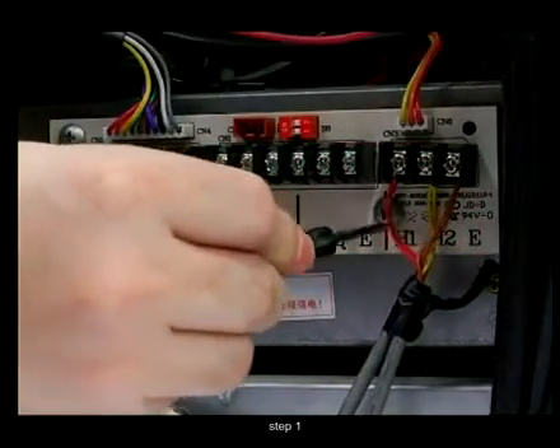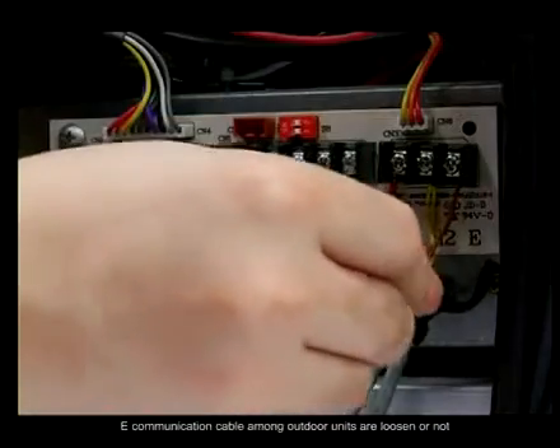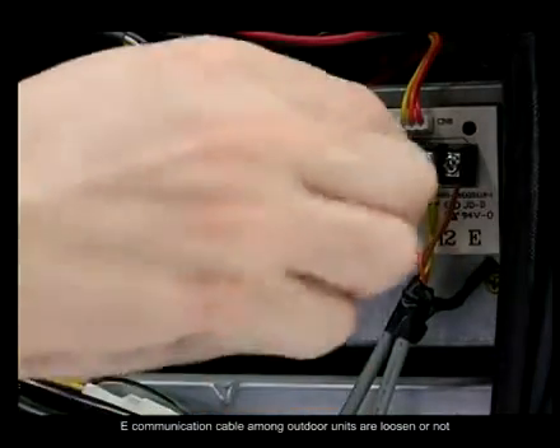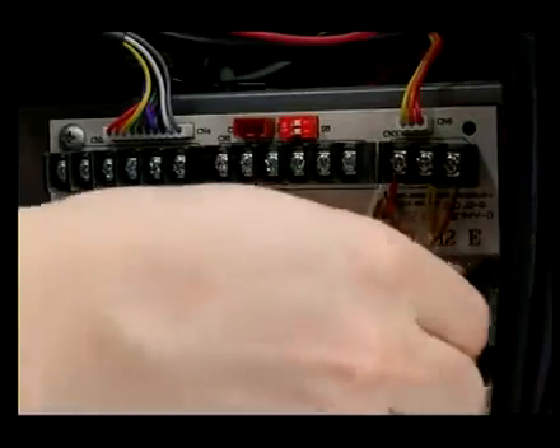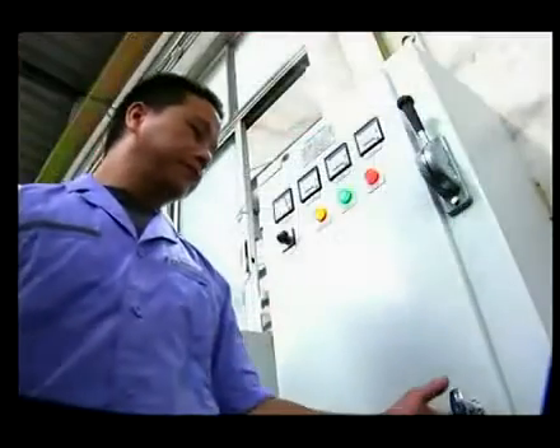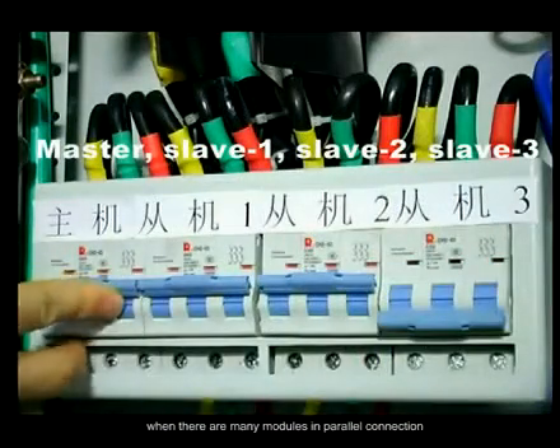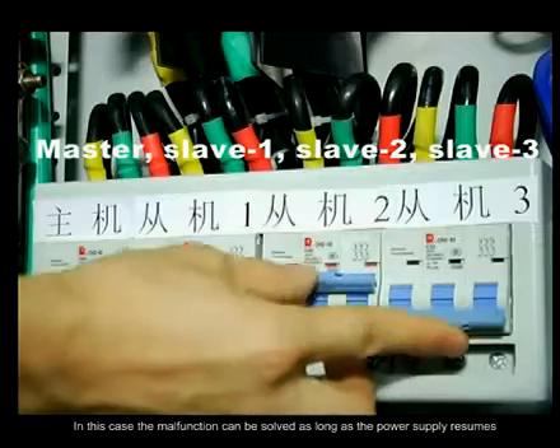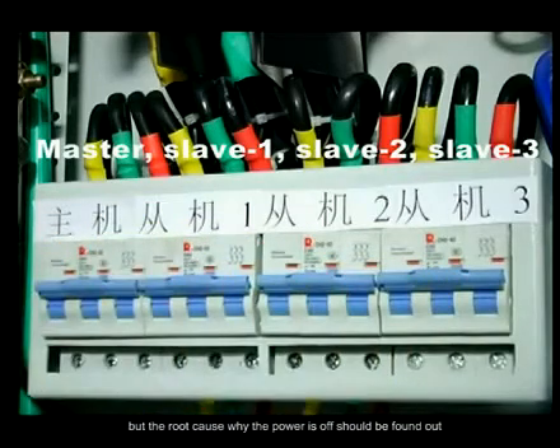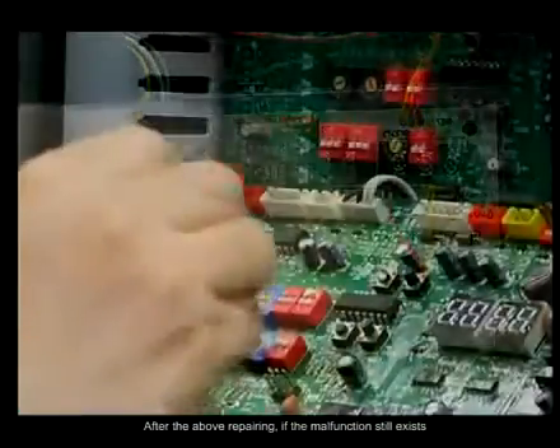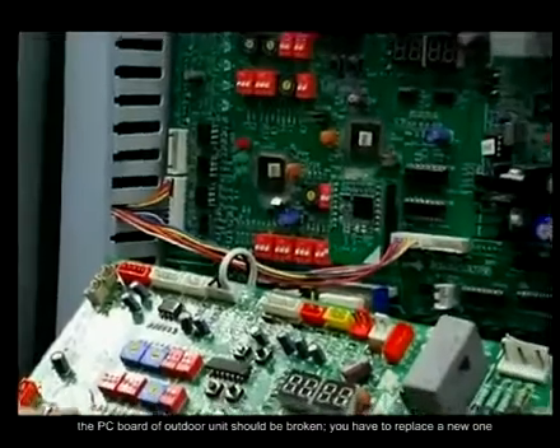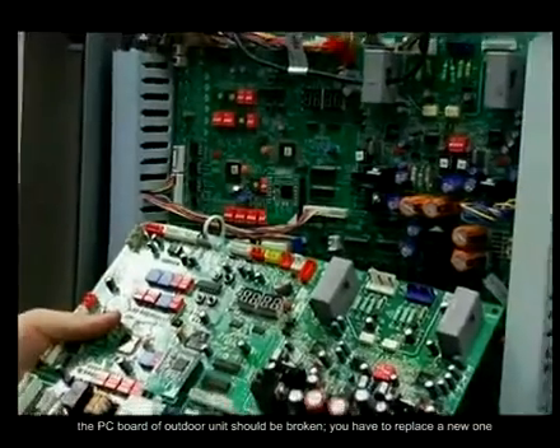Step 1. Check if the terminals of H1, H2, E communication cable among outdoor units are loosened or not. If loosened, please rewire the cable reliably. If it is normal, please go to the next step. Step 2. Check if some outdoor units are instantaneously powered off when there are many modules in parallel connection. In this case, the malfunction can be solved as long as the power supply resumes, but the root cause why the power is off should be found out. After the above repairing, if the malfunction still exists, the PC board of the outdoor unit should be broken. You have to replace a new one.